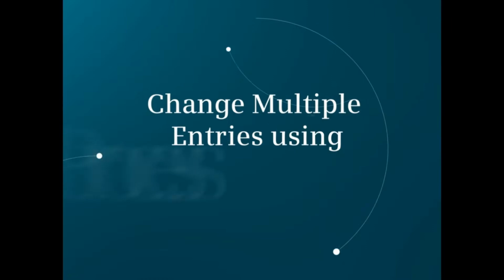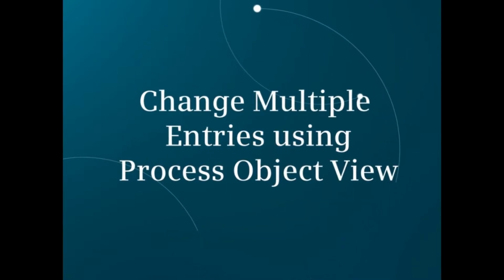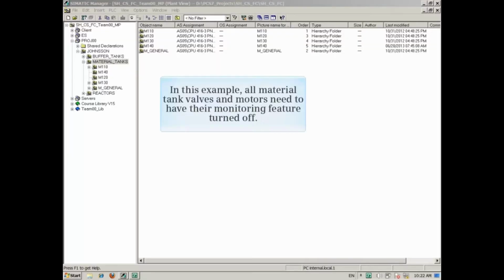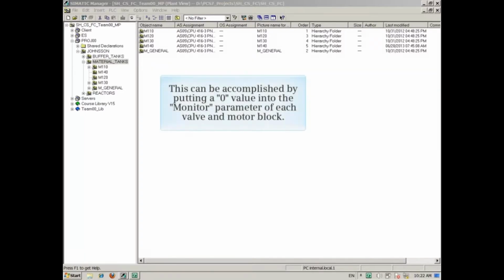This video will show an example of how to change multiple entries using the process object view. In this example, all material tank valves and motors need to have their monitoring feature turned off. This can be accomplished by putting a zero value into the monitor parameter of each valve and motor block.